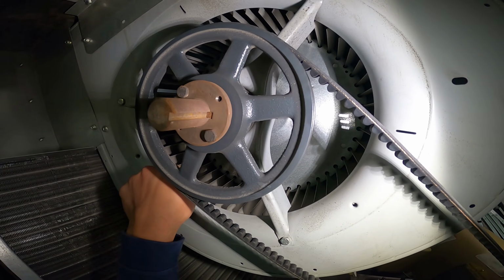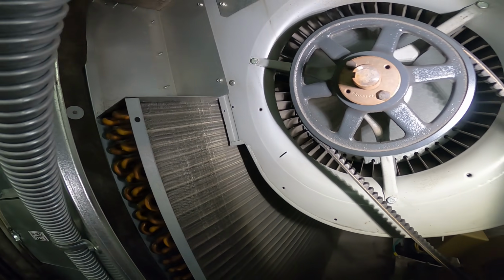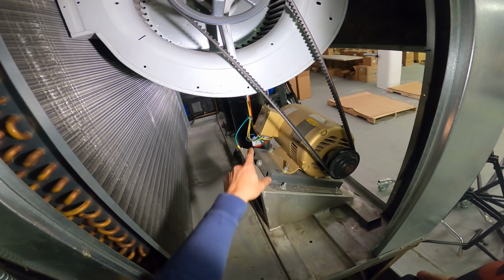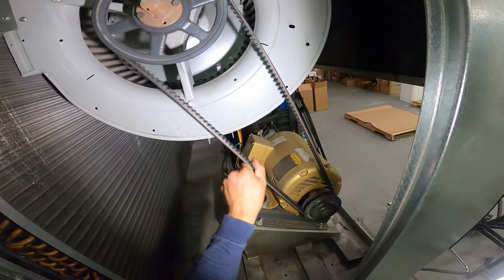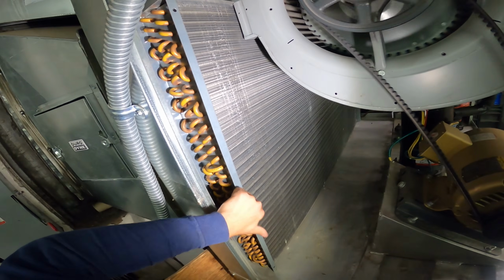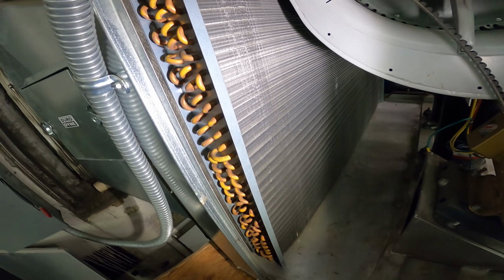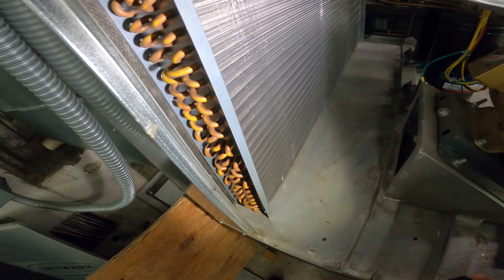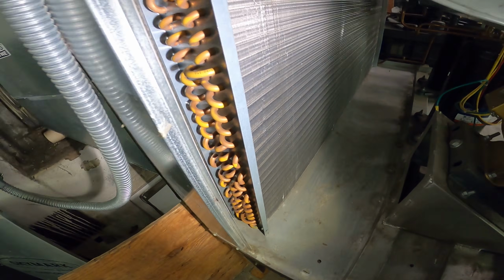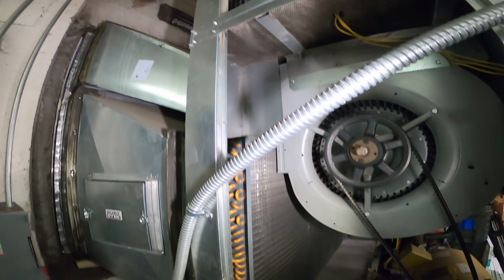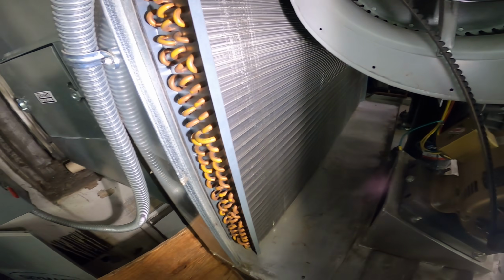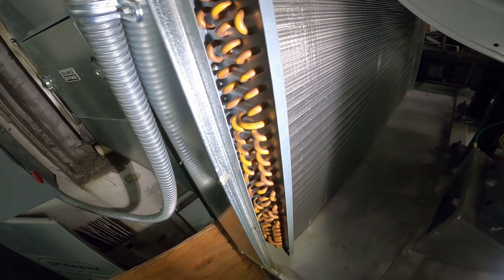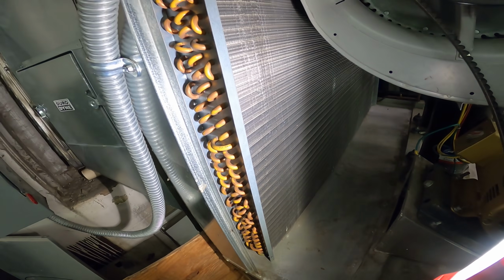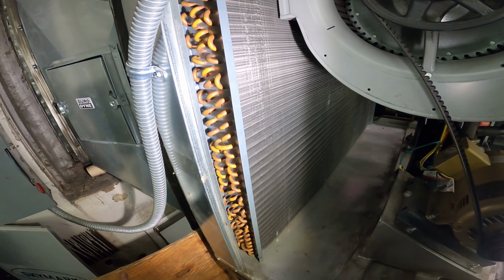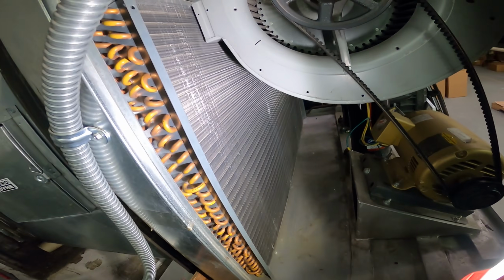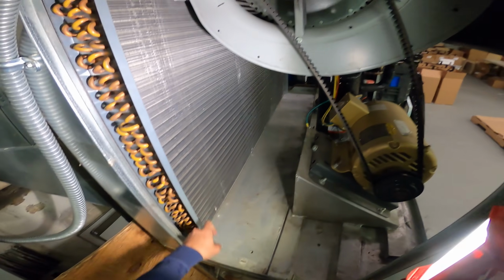Looks like a hamster's cage or something, you know, that they would run around through. So since we know our compressors are here, and this is our condensing unit, this coil is our condenser. This is our condenser coil. And what is a condenser coil, and what's the difference between an evaporator coil? There is none. It's just a copper coil with aluminum fins. And it's basically a heat exchanger. It's just used in different parts of the circuit. So this is our condenser coil.